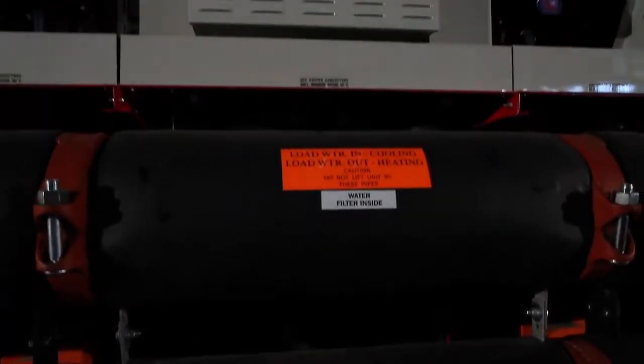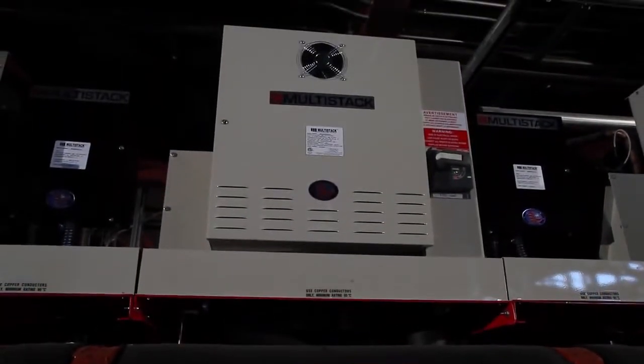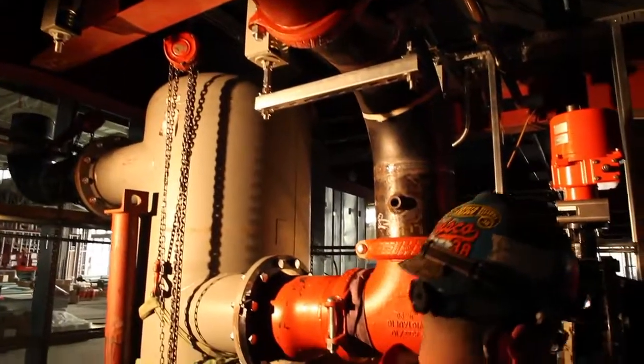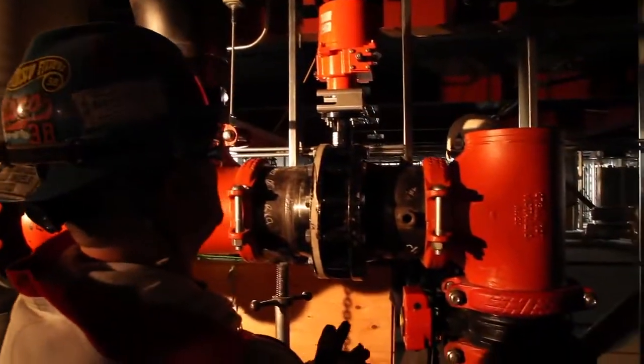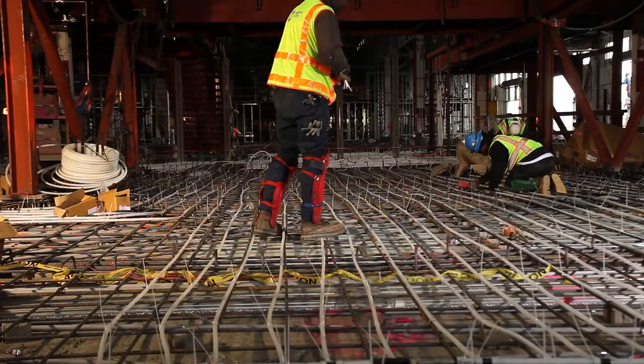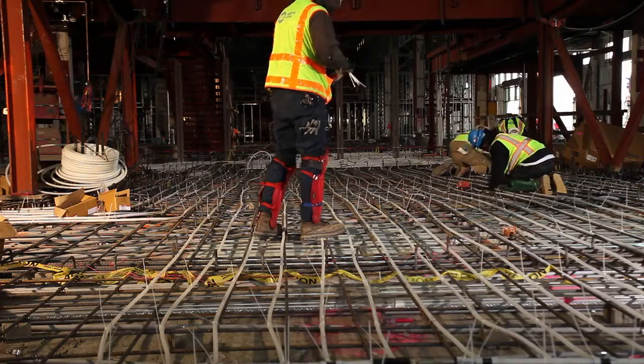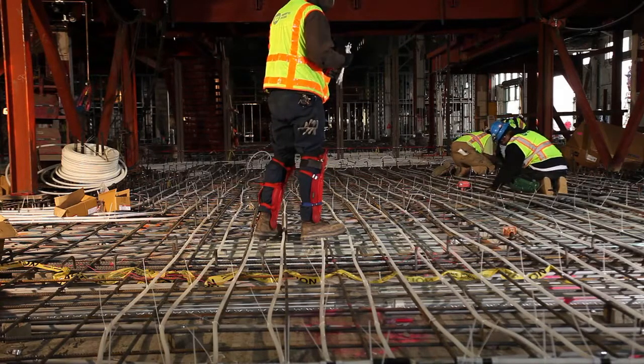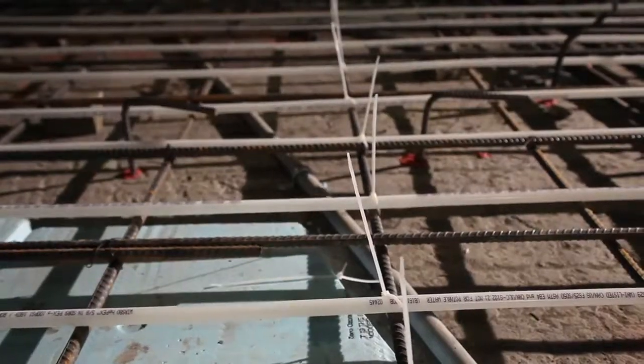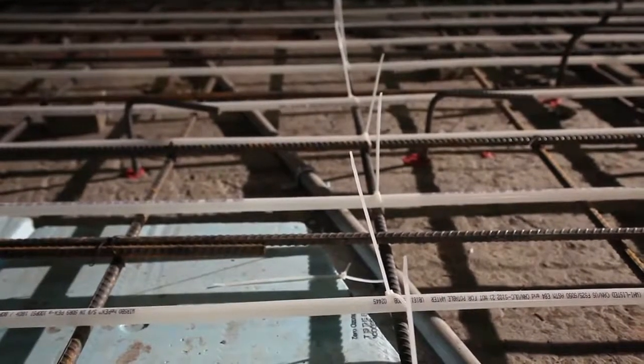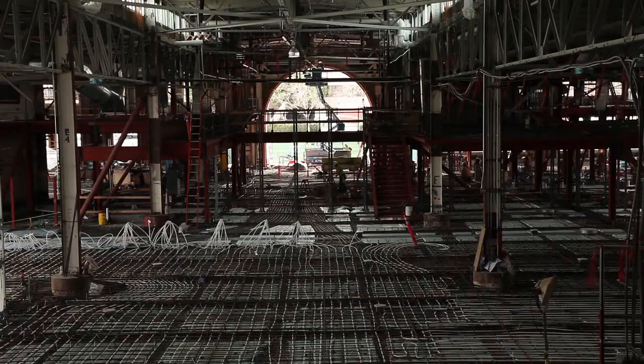These electric chiller heaters feed a 4-pipe system that carries hot and chilled water to a 200,000-foot network of cross-linked Uponor PEX-A tubing. The tubing is embedded in concrete slabs on 2 levels and spanning 82 heating and cooling zones, each zone with its own control valve and thermostat. It's a really comfortable system, and there's a desire to not sacrifice comfort for energy on this project.